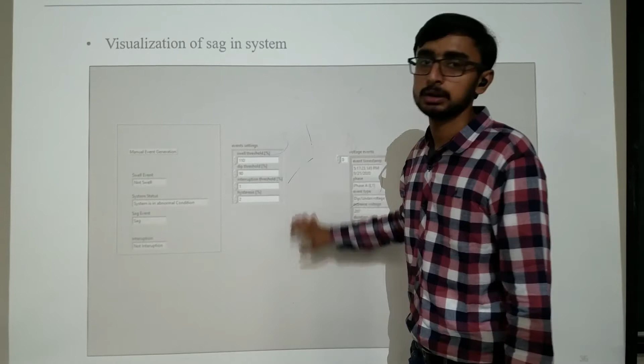Basically, now there is another objective, voltage swell. Voltage swell is defined by IEEE 1159 as an increase in the voltage greater than 1.1 pu. Voltage swell is almost always caused by an abrupt change in load or a circuit with a poor or damaged voltage regulator.